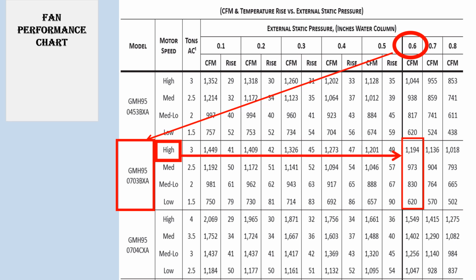So we're over a little bit, but we know that to stay at a 59-degree temp rise, we need 674 CFM on low speed. At the 0.6, we would need 600. We'd only be getting 620. We can get 817 though at medium low, and so on and so forth. And then you just have to interpolate a little bit what those rises would be with a little more or a little less airflow.